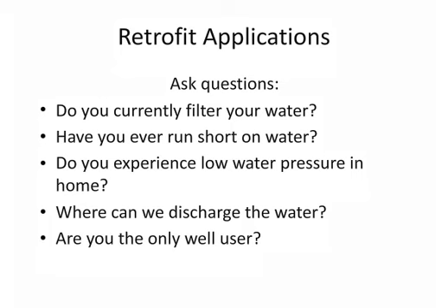Retrofit applications. Folks, I can tell you, when I got phone calls from homeowners saying, hey, I have fabulous well water, and I want you to come up and install a geothermal heat pump, well, that didn't cause me to jump behind the windshield of my vehicle and drive up there. It meant that I had to ask them a lot of questions. For example, do you currently filter your water? And if the response was yes, I would say, well, what would you be filtering if you have such great well water?